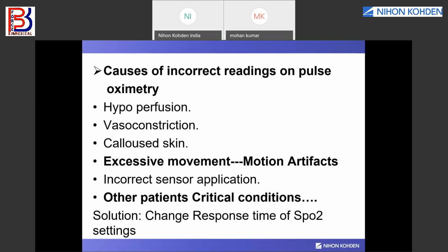As you can see in the graph, the thick line shows the SpO2 reference. The reference is set for SpO2 reading in a thick line. And there is a thin line, which is the response if you choose fast response in SpO2 setting in the patient monitor. And there is a dotted line that shows the normal SpO2 setting. If everything is good, the site is good, arterial flow is good, you can set it to normal response.